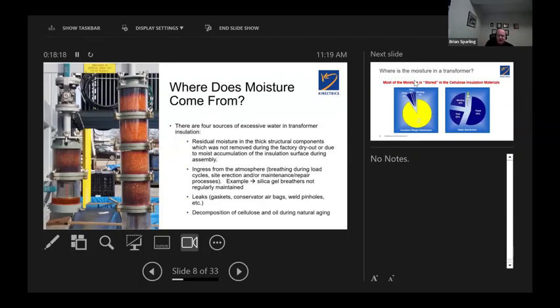And the decomposition of the paper and the oil during its natural aging process inside. When paper degrades in the transformer, it produces its own worst enemy. It's cellulose. And cellulose is basically a chain of glucose molecules all held together. And when they break because of moisture and heat, they break away, make a sugar, glucose. When it breaks apart, you have produced water. 3 parts water for every break in the cellulose chain. So, and there's billions, of course, in there. So that's where it produces water. It's a natural occurring phenomena that the only way you control it is to try to control the temperature inside and the moisture content.